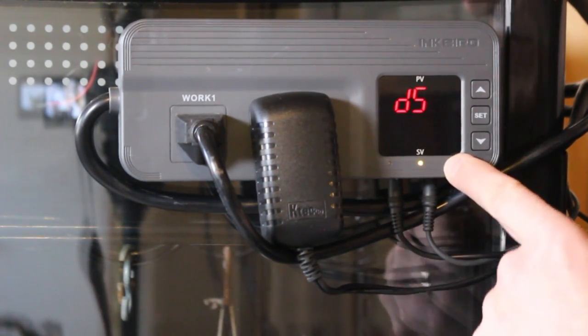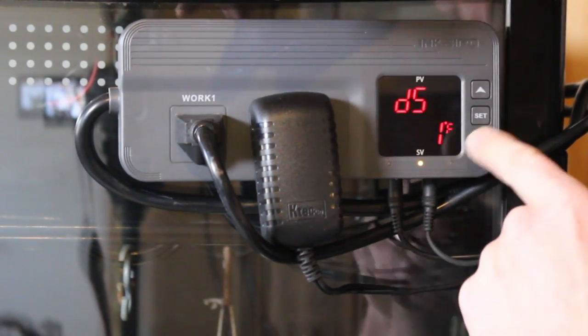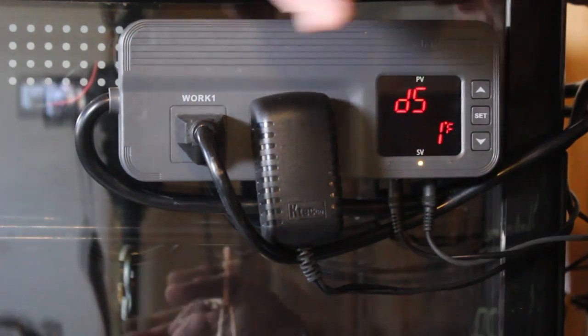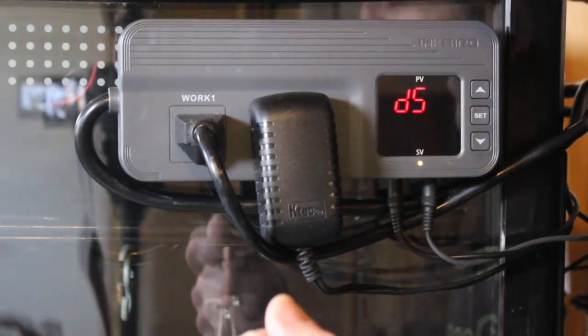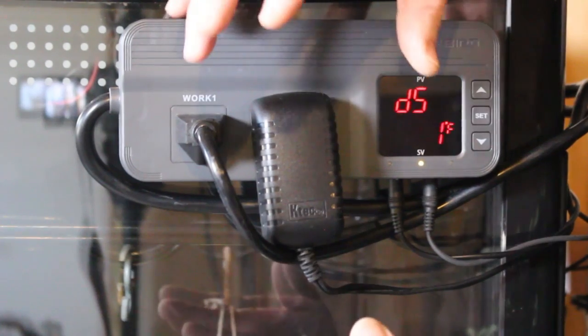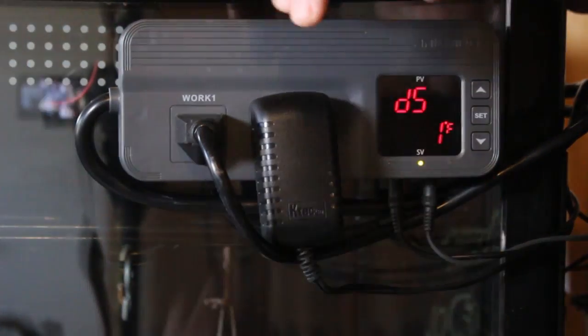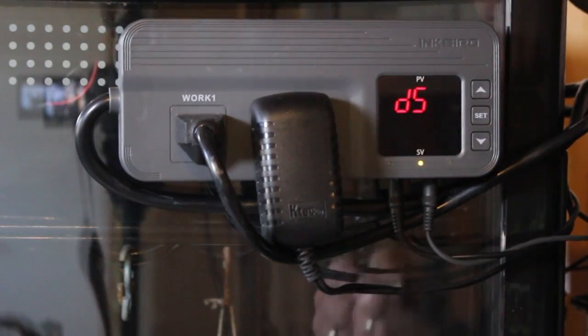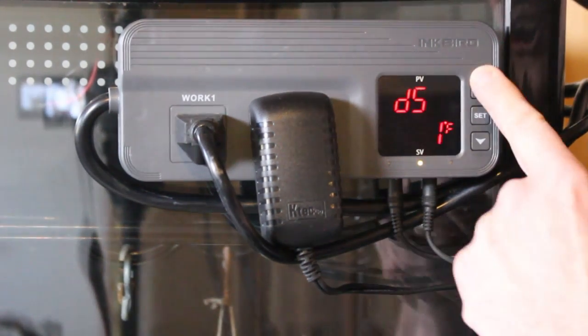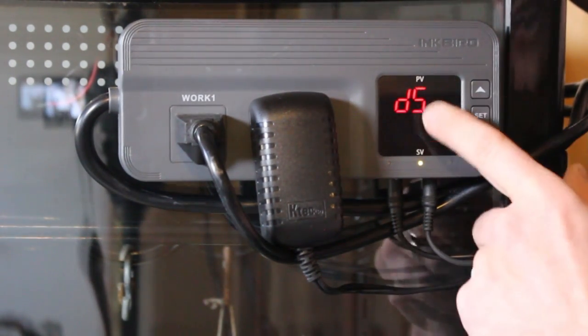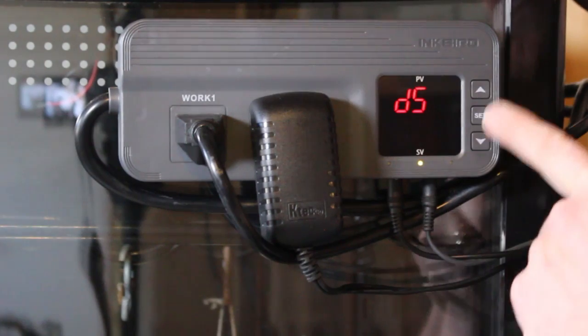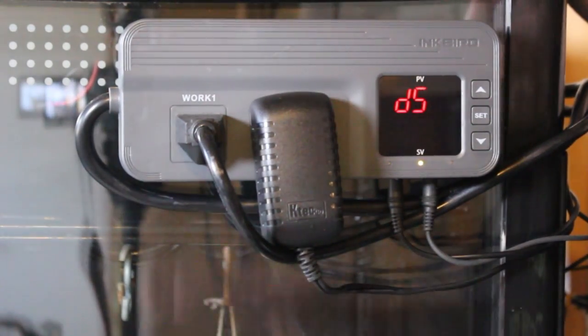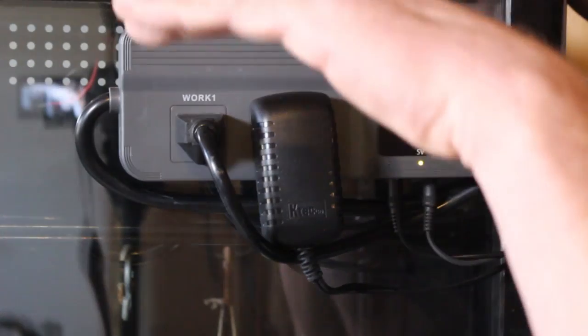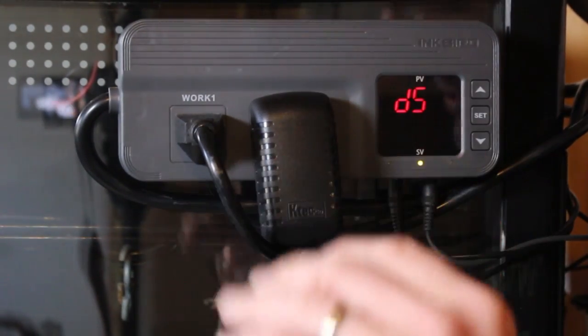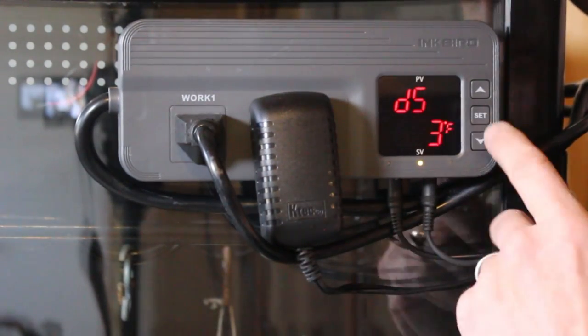You don't want it so that if I've got it set to 65 and the temperature goes to 64, the compressor immediately comes on and chills the refrigerator, and then it gets to 65 and immediately turns off, because the compressor is going to keep coming on and off, and you're going to burn your equipment out too quickly. So keep your temperature differential maybe 3 degrees, just so it'll get up to 68, and then it'll cool down to 64, and then it'll cool up to 67. So you're sort of around 65 degrees, but it doesn't have to be exact.